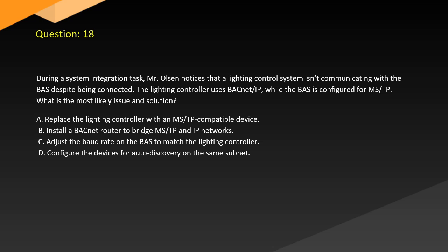Question 18. During a system integration task, a technician notices that a lighting control system isn't communicating with the BAS despite being connected. The lighting controller uses BACnet while the BAS is configured for MSTP. What is the most likely issue and solution? A. Replace the lighting controller with an MSTP-compatible device. B. Install a BACnet router to bridge MSTP and IP networks. C. Adjust the baud rate on the BAS to match the lighting controller. D. Configure the devices for auto-discovery on the same subnet.